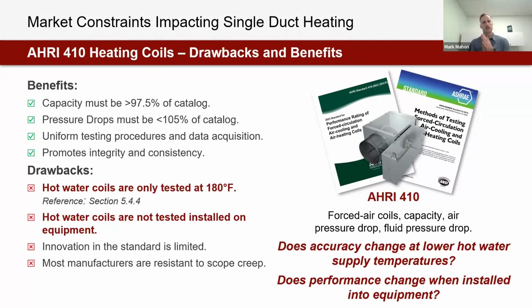And the truth is, this standard is not only hot water coils, it's water coils, there's DX, there's steam, there's refrigerant, and then there's latent and sensible cooling. So it's a wide breadth within the standard. And then when we focus in on any particular product segment within there, it's pretty high level and there are some drawbacks. So hot water coils are tested at 180 degrees only. Hot water coils are also not tested installed on equipment. So that means the catalog data you see for a single duct hot water coil, it's installed in ductwork with perfect uniform airflow. It's not actually installed within the terminal itself.